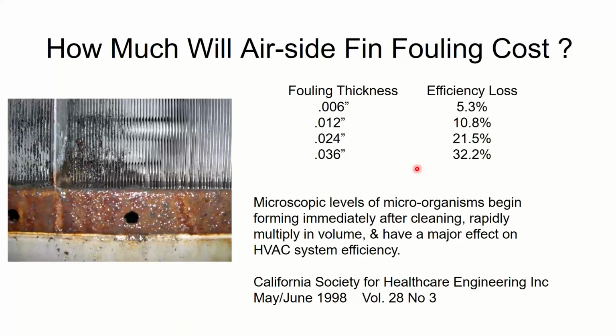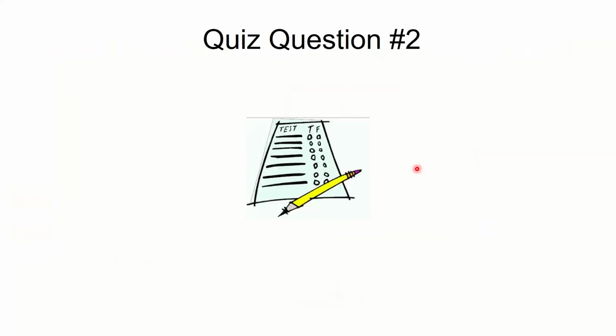There's also a benefit, since this is an energy topic we did for Peoples and North Shore Gas, there's actually an electrical benefit to keeping the coil clean. It will improve airflow because the dirt won't be there blocking it, and it'll also improve heat transfer between the refrigerant and the air, or between the water and the air if it's a hydronic coil. So I will get some improvement in efficiency by keeping my coil clean. So not only is it less gross and has less things growing on it, but I can also save a couple bucks.